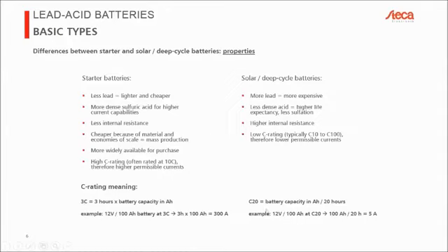Now let's take the same example if we have the number behind the C, which is much more typical of a stationary solar deep cycle battery. In this example, we have C20, and instead of multiplying, we divide the two numbers. We take the battery capacity and divide it by that number in hours. So we have a 12-volt battery, 100 amp hours, but instead of being rated at 3C, it's rated at C20. Now we divide: the capacity divided by 20 is 5 amps. That's the amount of current we can charge, though typically discharge is the rating given for this particular battery.